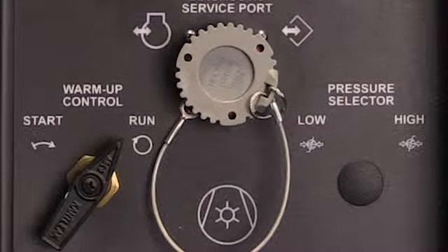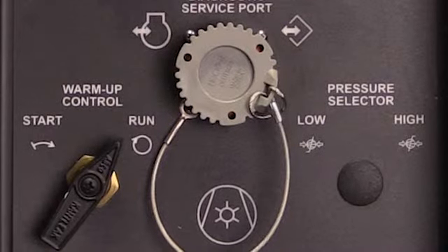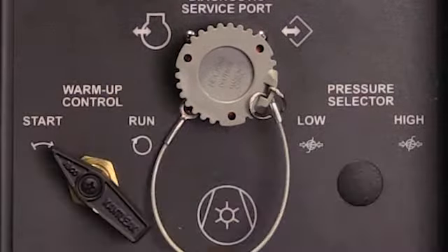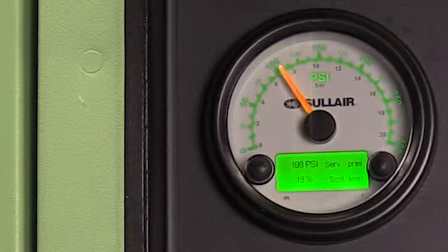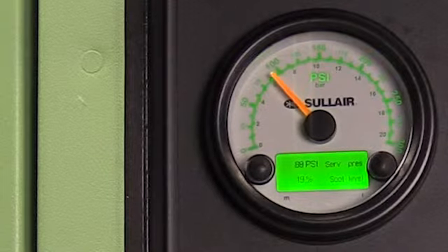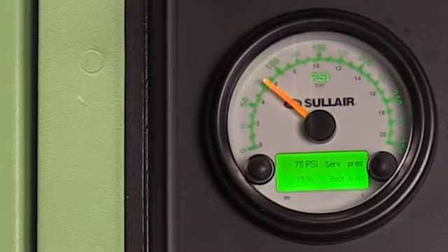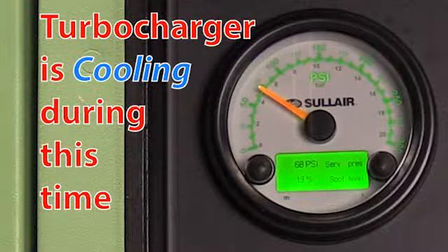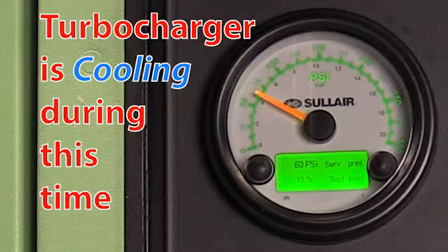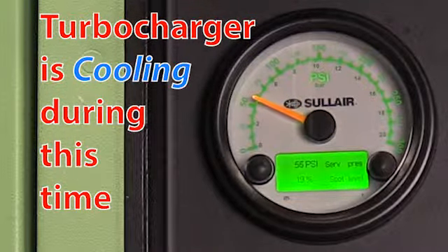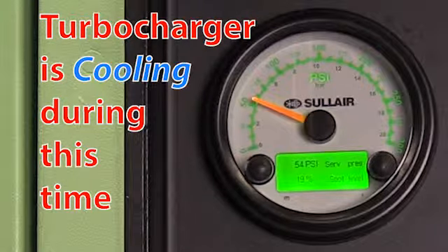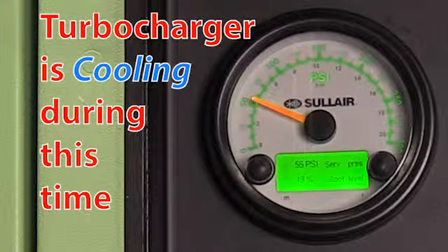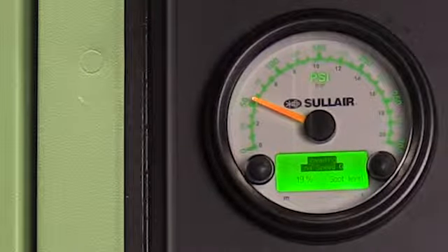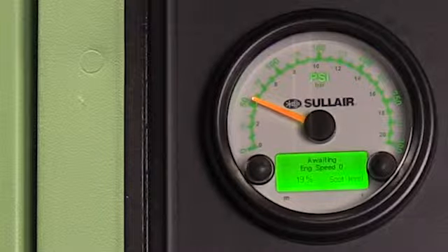Take the start-run switch or valve and turn it to the start position. By transitioning the start-run valve from the run position to the start position, it puts the compressor in a forced unloaded state. It's recommended that you leave it like this for a couple minutes to help cool off the engine turbo. Once you have given the turbocharger a significant time to cool off, simply turn the ignition switch to the off position. At this point, the engine will shut down and the panel will power off.